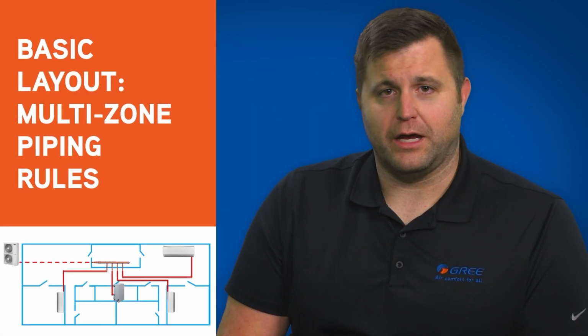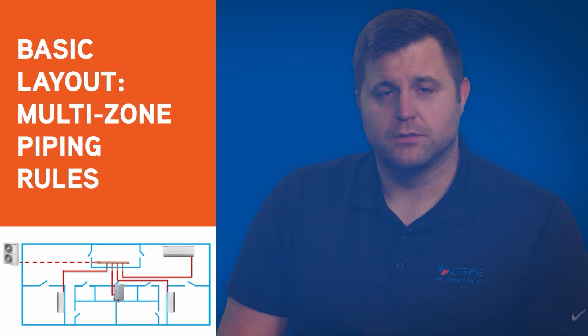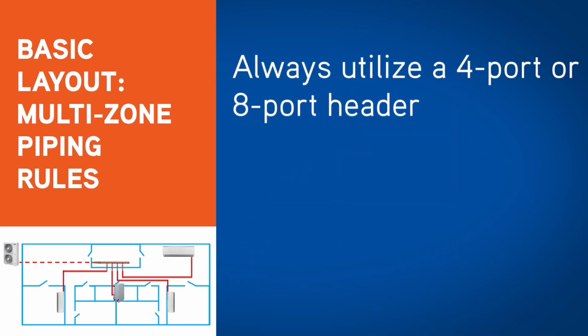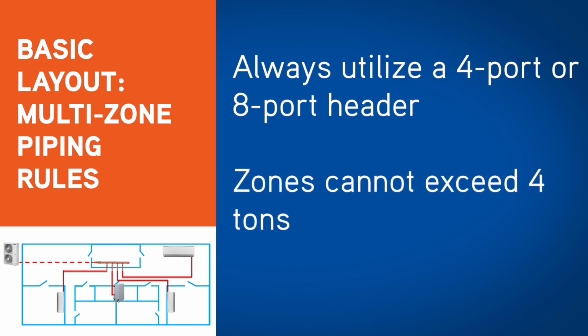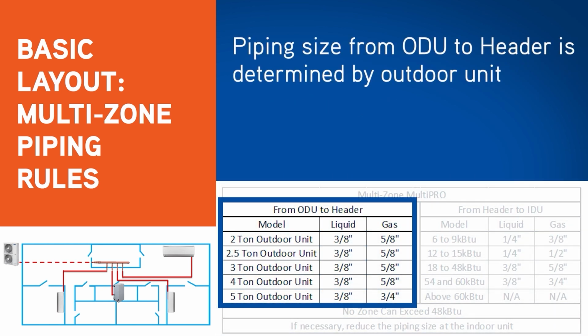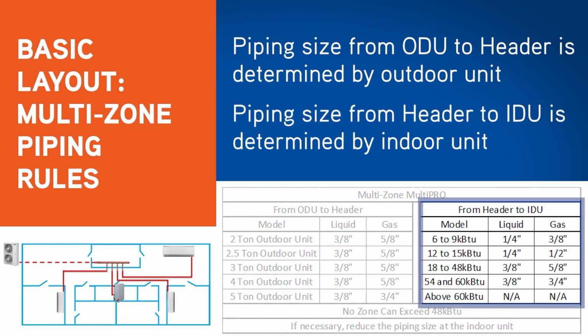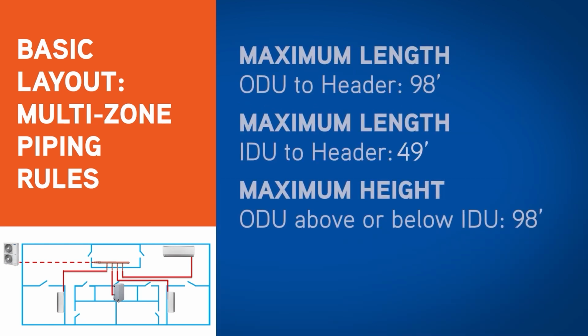Even at its most complex, the multi-zone MultiPRO basic layout is still simple with easy to follow rules. This layout will always utilize a 4-port or 8-port header. Each zone cannot exceed 4 tons. As before, the piping size from the outdoor unit to the header is determined by the capacity of the outdoor unit. The piping sizes from the header to the indoor units are determined by the indoor unit capacity. The piping length limitations are the same as the dual zone basic layout.